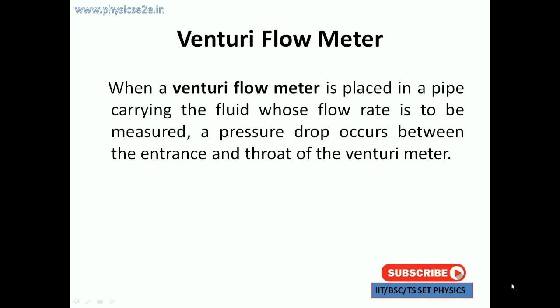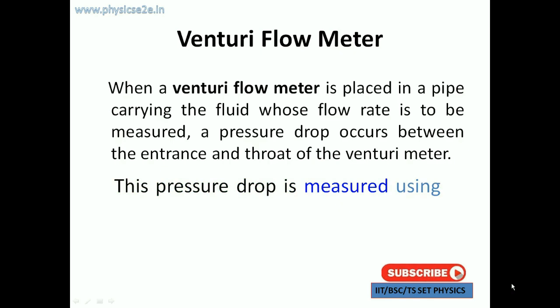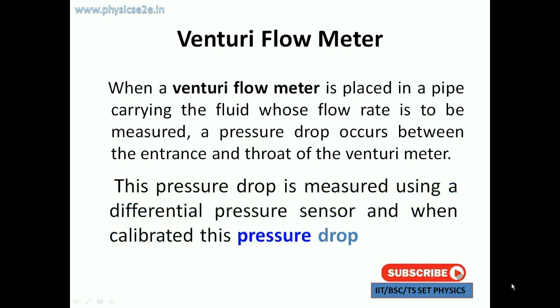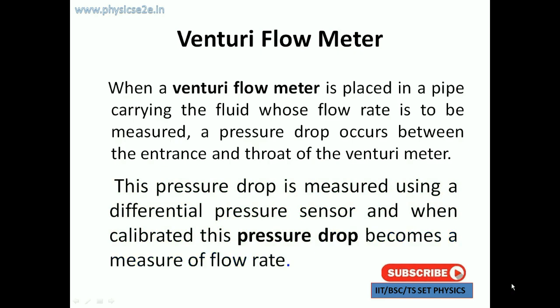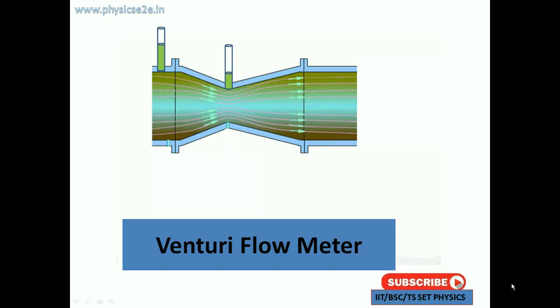The Venturi flow meter is placed in series in the pipelines of which fluid flow rate is to be measured. The throat and inlet are the major parts of the Venturi flow meter. This pressure drop is measured using differential pressure sensors, and when calibrated, the pressure drop becomes a measure of flow rate.